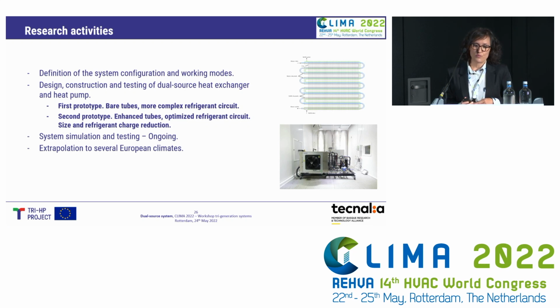For the dual source heat pump, we constructed a first prototype with bare tubes and a somewhat more complex refrigerant circuit. We have tested it, and then we also built a second prototype which included enhanced tubes, and the refrigerant circuit was optimized. This allowed us to reduce the unit size and also achieve an important refrigerant charge reduction. Also, the system is simulated and tested. This is ongoing now. And finally, extrapolation of the simulations for several European climates will be done.